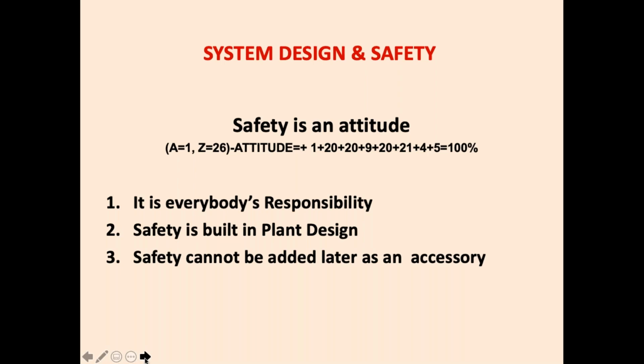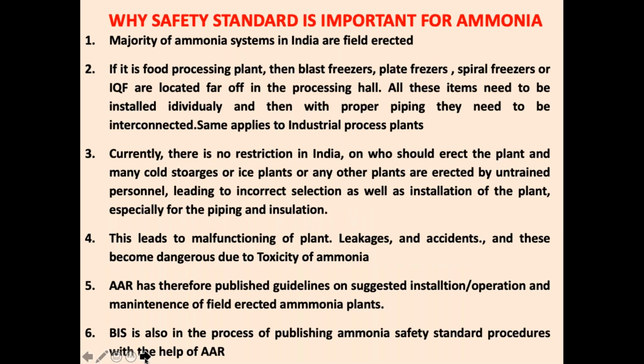So why is a safety standard important? For ammonia, why is it so important? Because the majority of ammonia systems are field erected. If it is a food processing plant, then blast freezers, plate freezers, IQFs are all located far off in a processing hall, and these are away from the machine room. They are installed individually, and the proper piping is done to interconnect them. The same applies to industrial process plants. The plant can be as far away as 1 kilometer from the process area.